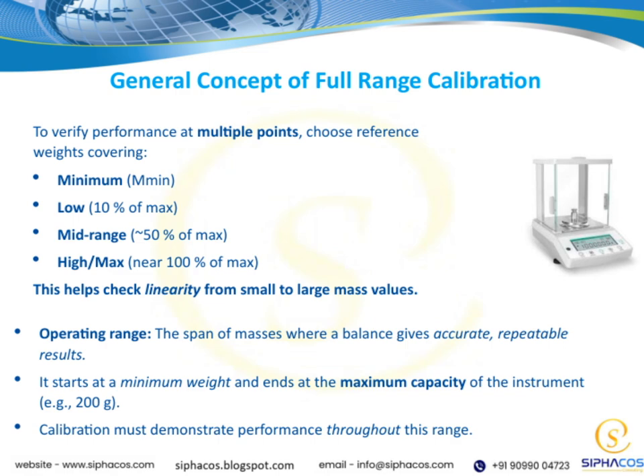To do this effectively, you should choose reference weights that cover several key points. The minimum weight, a low point around 10% of the maximum, the mid-range around 50%, and the high or near maximum, close to 100%. Using these points helps us verify the linearity of the balance. That is, ensuring it responds proportionally across small and large weights. This way, we can be confident that the instrument is accurate no matter what size of mass we're measuring within its operating range. So, in essence, understanding and validating this full range is crucial for reliable measurements and overall calibration accuracy.